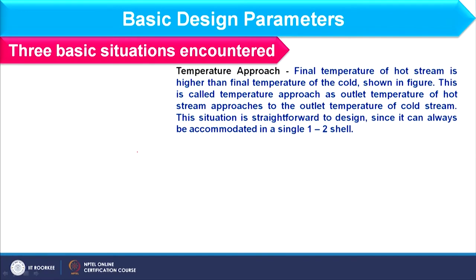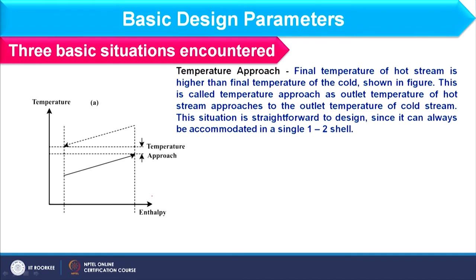To understand how to choose the FT correction factor, we introduce the concept of temperature approach. There are three basic conditions. The first is when we have sufficient temperature approach — that is, the difference between the outlet temperature of the hot fluid and the outlet temperature of the cold fluid. This is illustrated in a diagram showing the hot fluid temperature decreasing and the cold fluid temperature increasing along the exchanger length.